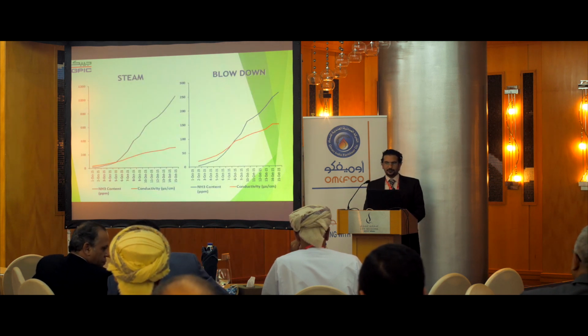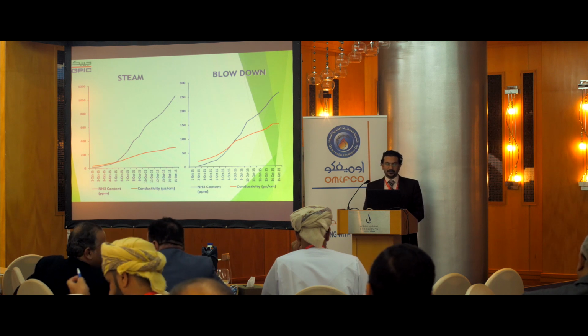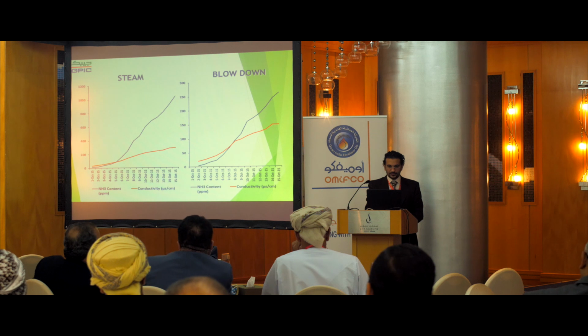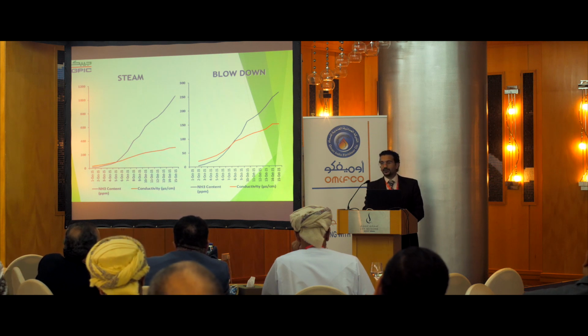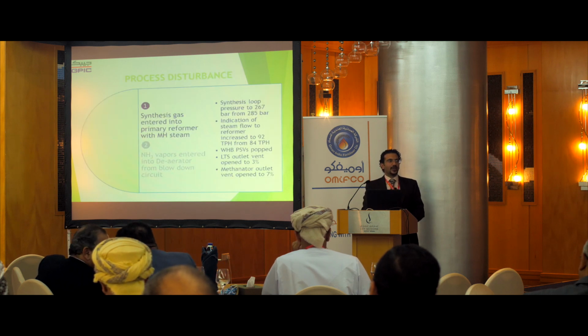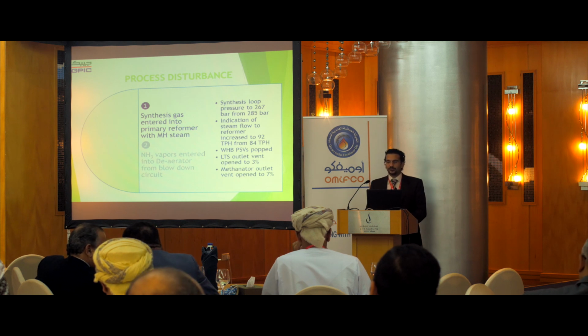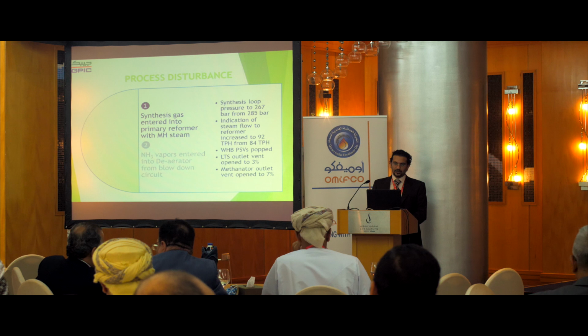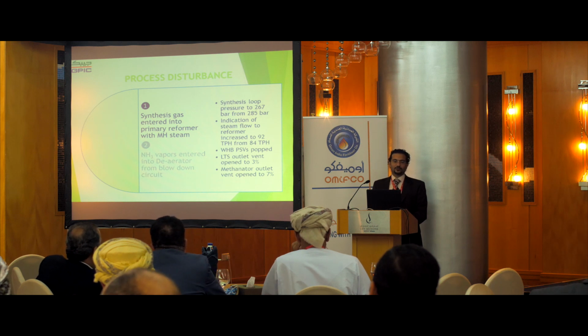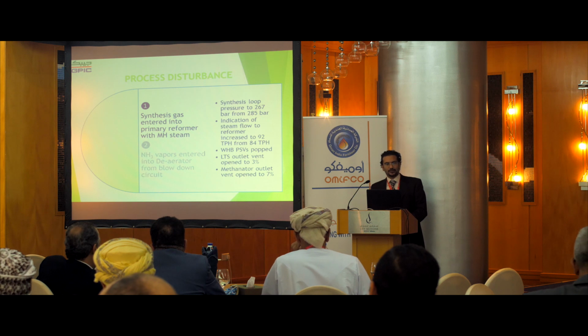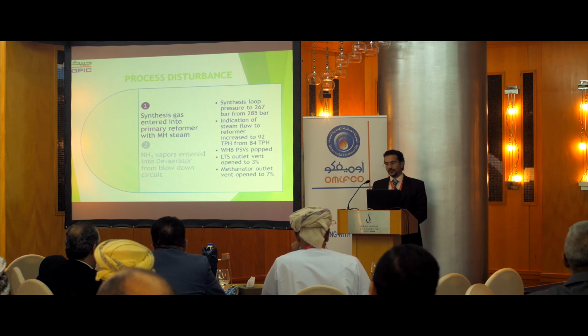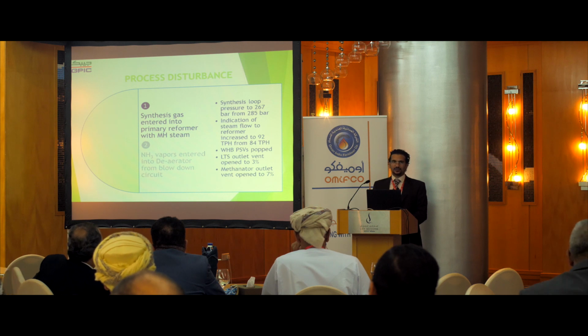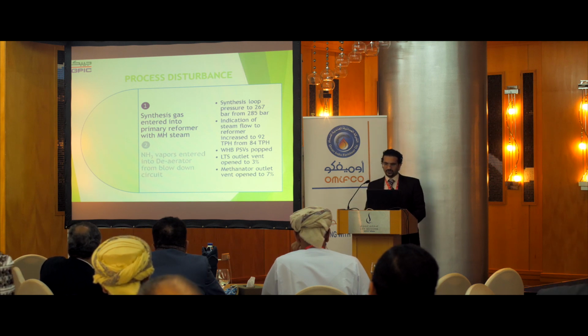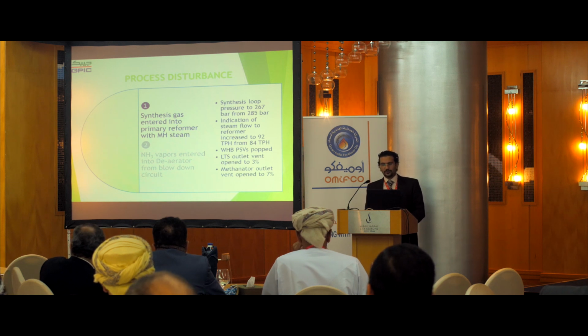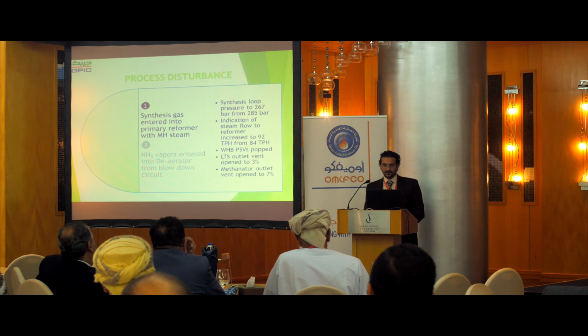So this is the steam and the blowdown conductivity and ammonia content over the 2 weeks, and how it increased drastically throughout the weeks. When the failure happened, it disturbed our plant steam and our gas a lot. Synthesis gas entered the primary reformer with the MH steam. The loop pressure decreased drastically by about 20 bar, from 285 to 267. The indication of the steam flow to the reformer increased by almost 9 tons.